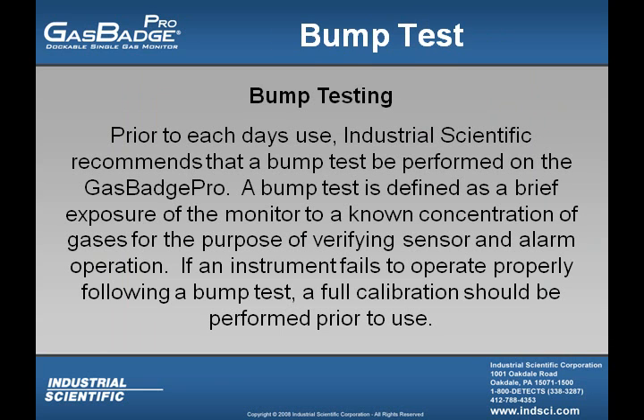Now onto the third step of operation, which is the functional test, or the bump test. Prior to each day's use, Industrial Scientific recommends that a bump test be performed on the GasBadge Pro. A bump test is defined as a brief exposure of the monitor to a known concentration of gases for the purpose of verifying sensor and alarm operation. If an instrument fails to operate properly following a bump test, a full calibration should be performed prior to use.